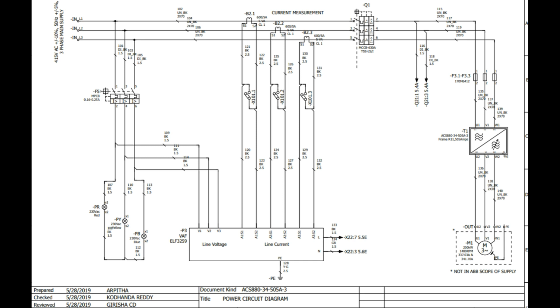So there are three different CTs, B 2.1, 2.2, 2.3, and the ratings are also given, 600 by 5 amps, that is the primary and secondary ratings of the current transformers. And this will go to again a VAF digital meter, and this will show you the line currents. So with the help of line voltage and line current, this meter will give you three readings, that is voltage, ampere and frequency. Next, going ahead with current measurement CT, there is Q1 MCCB 630 amps, and further there are two tappings taken which we will deal with in another page.